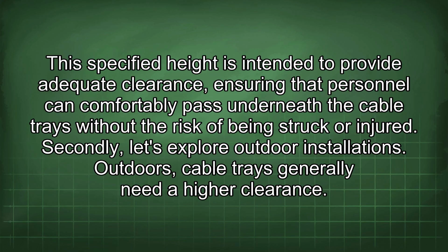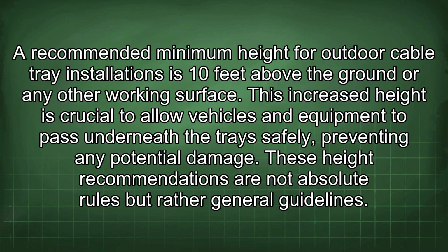Secondly, let's explore outdoor installations. Outdoors, cable trays generally need a higher clearance. A recommended minimum height for outdoor cable tray installations is 10 feet above the ground or any other working surface. This increased height is crucial to allow vehicles and equipment to pass underneath the trays safely, preventing any potential damage.